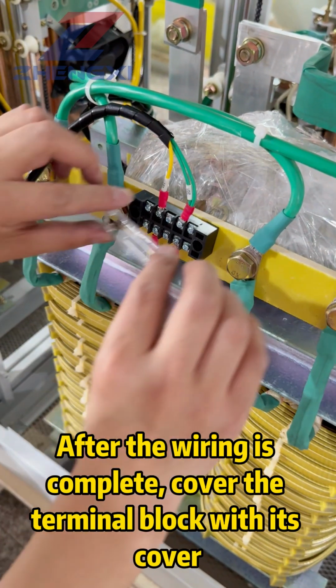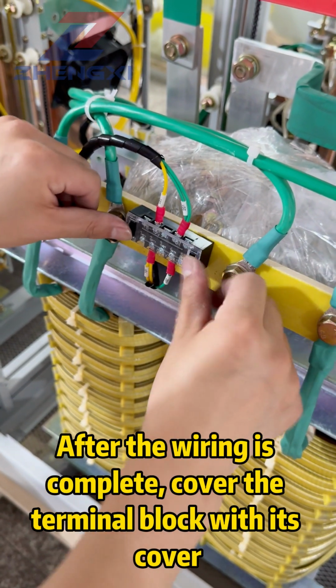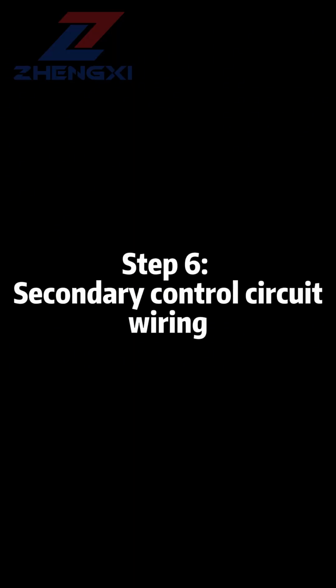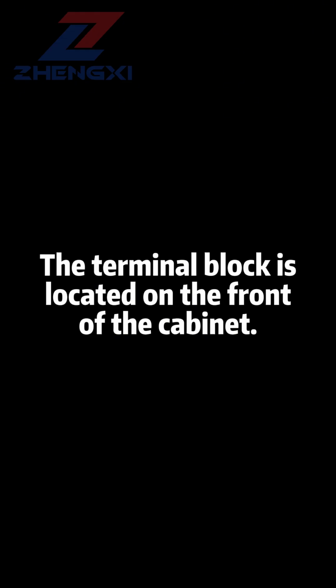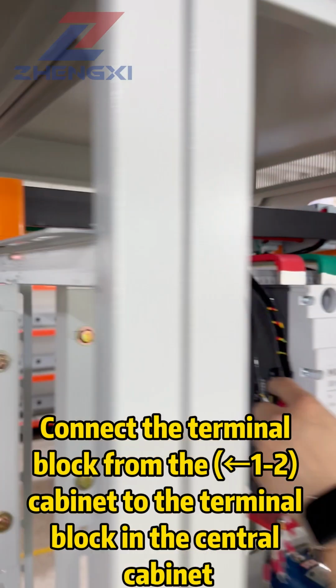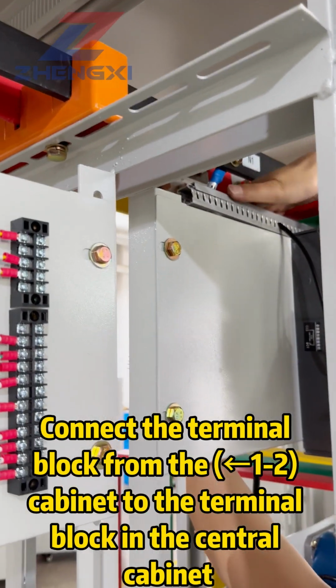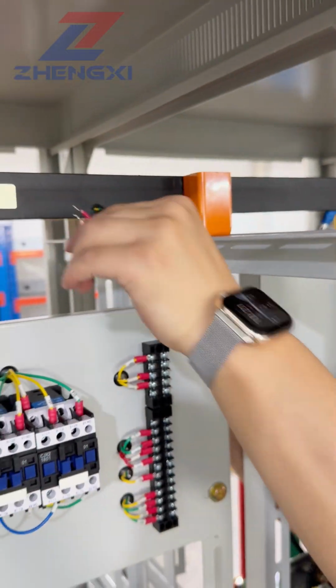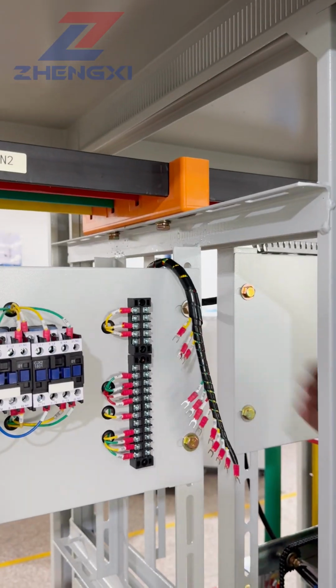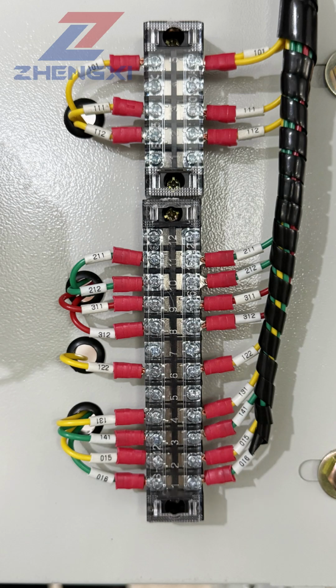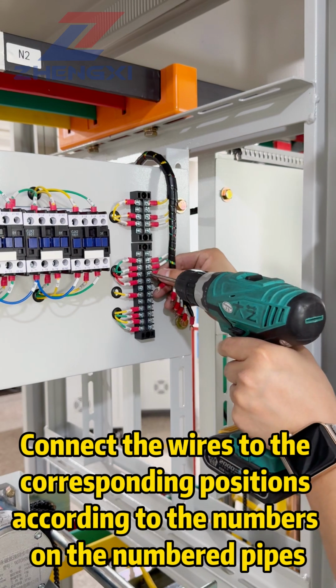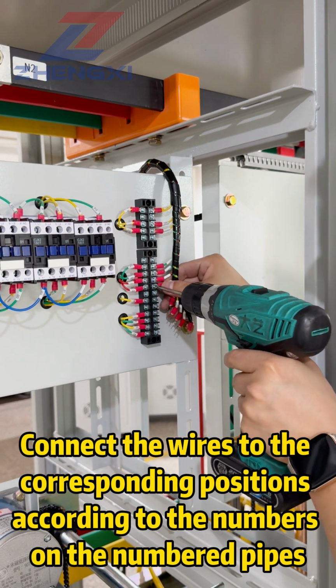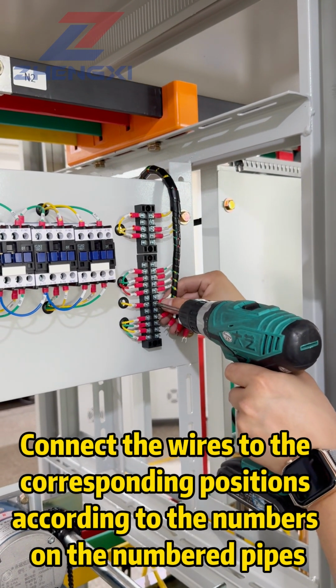After the wiring is complete, cover the terminal block with its cover. Step 6. Secondary control circuit. Wiring. The terminal block is located on the front of the cabinet. Connect the terminal block from the 1 and 2 cabinet to the terminal block in the central cabinet. As shown in the diagram, connect the wires to the corresponding positions according to the numbers on the numbered pipes.